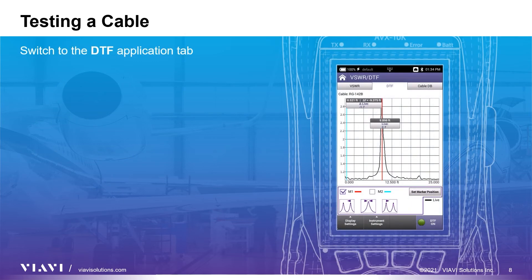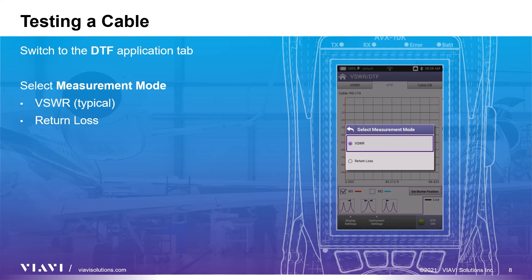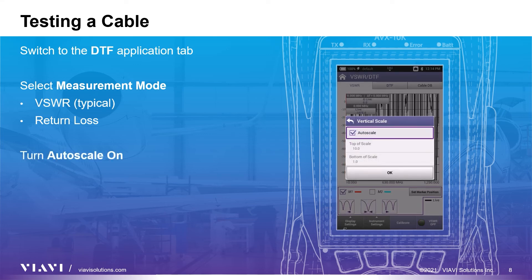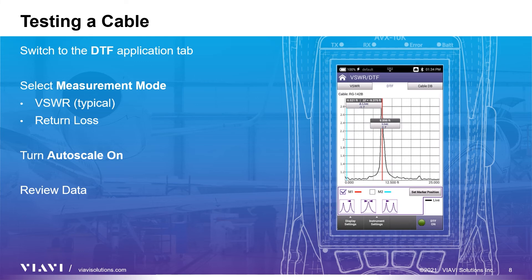Please see the manufacturer's specifications for tolerances. This application can also help determine faulty cables or connections. Click on the DTF tab. Connect your cable under test directly to the SWR port on the AVX10K, and for best results set measurement mode to VSWR and turn Vertical Auto Scale ON. If you have an open or short in the cable, it will look similar to this.